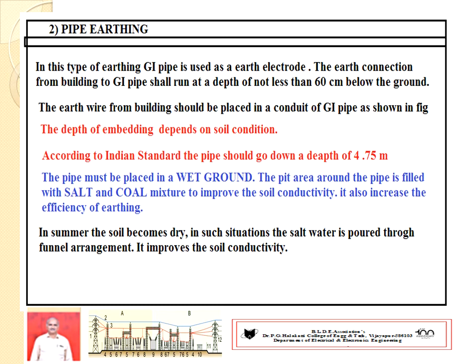Number 2, pipe earthing. In this type of earthing, instead of a plate structure, a pipe structure is used as the earth electrode. Commercially, again, GI pipes are used. The earth connection from the building to the GI pipe should run at a depth not less than 60 centimeter below the ground. The earth wire taken from the building should be connected to the GI pipe as shown in figure. Depth of embedding always depends upon soil condition. If soil possesses low resistance, the minimum standard depth of embedding should be used. If soil possesses high resistance, then we have to increase the depth of embedding. It may be around 4.75, or approximately you can remember 5 meters.